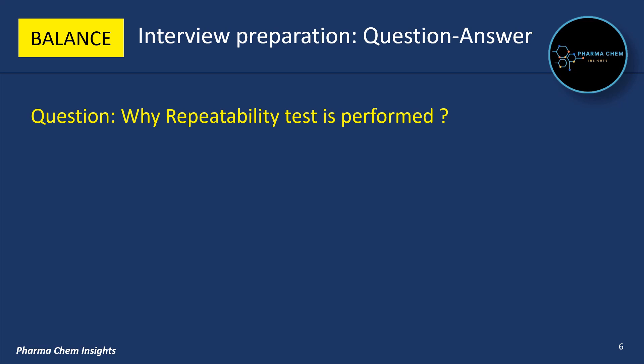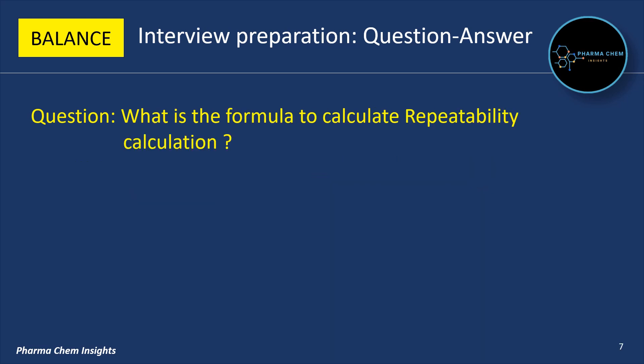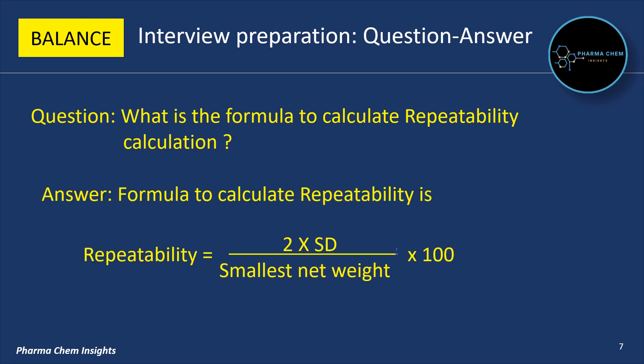Next question: why is the repeatability test performed? A repeatability test is performed to check the ability of the weighing balance to give the same results for the same object under the same conditions every time. The formula to calculate repeatability is: Repeatability = (2 × SD / Smallest Net Weight) × 100, where SD is the standard deviation.